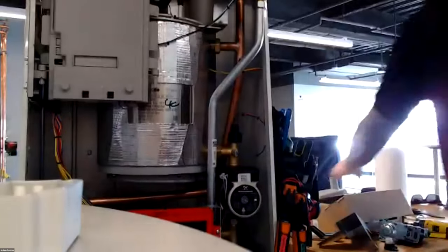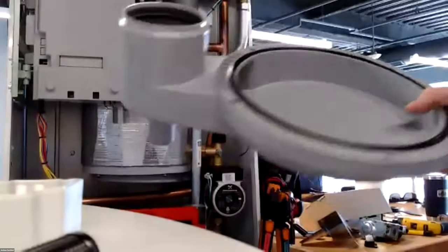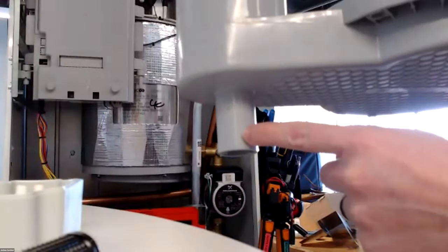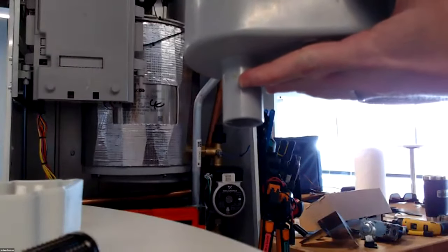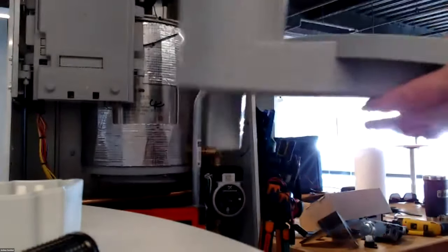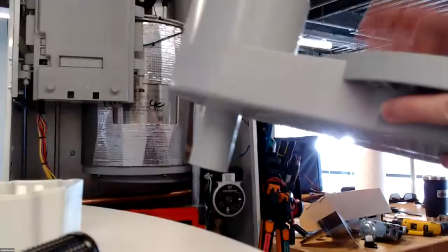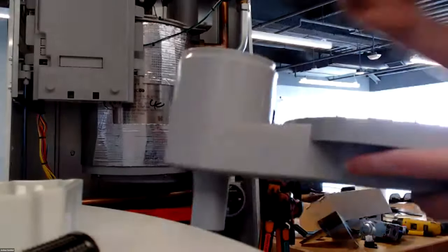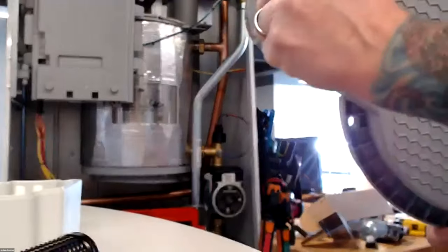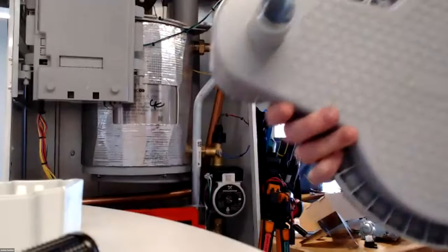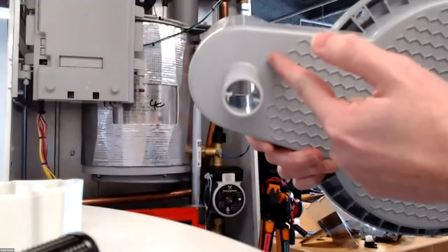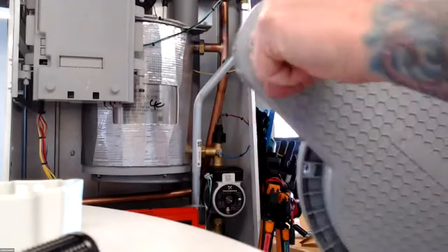So this is the condensate pan right here. You'll have this nipple right here. Jacket will be about right here. When you get a heating only boiler, open up the box, it'll be laying on its back. Put your bracket on the wall. Take that boiler from the box to the wall. Try not to set it down. You can set it down carefully, but I've seen guys slam it down or drop it, and they'll hit the ground with this and crack this nipple up into the pan. I've seen it happen twice. It is pretty tough, but if you drop it hard enough, you can break that.